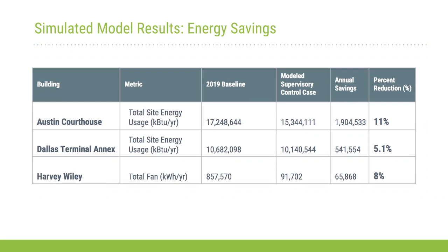For Harvey Wiley, we calculated the savings in Python against the 2019 baselines. We grabbed manufacturer fan curves as well as horsepowers of fans and a lot of BAS data to accurately model those. You'll see higher savings in Austin due to a higher EUI and some retro-commissioning issues initially.